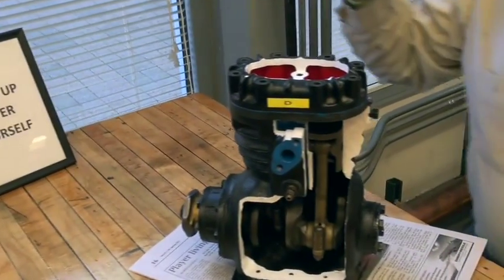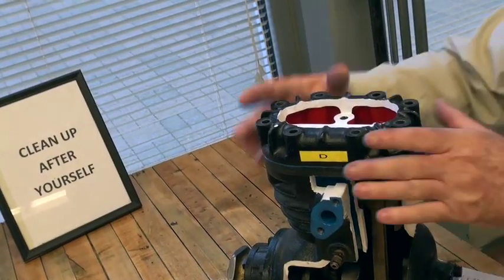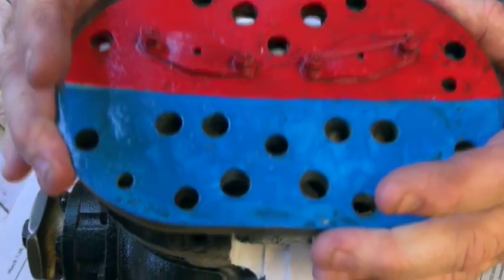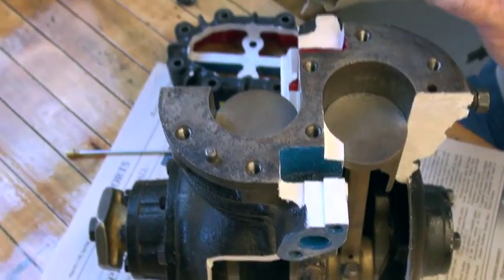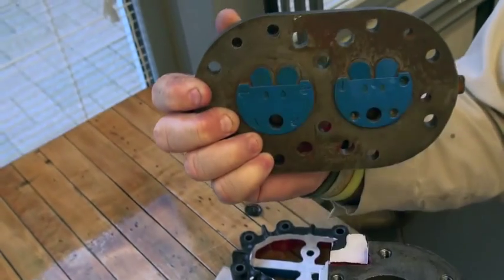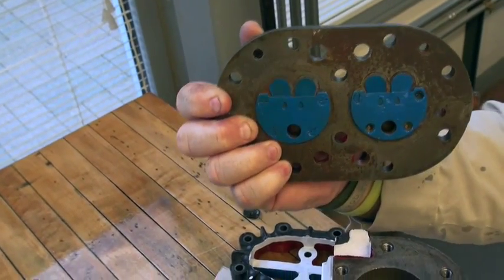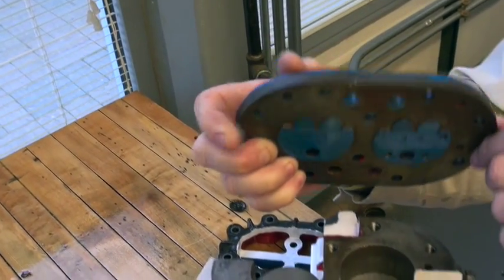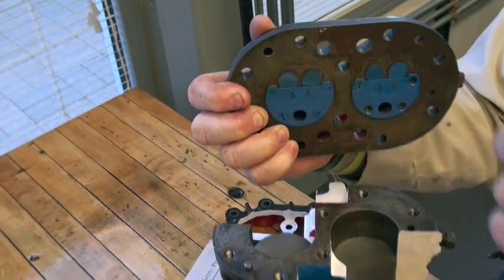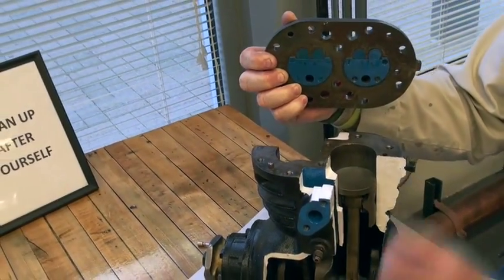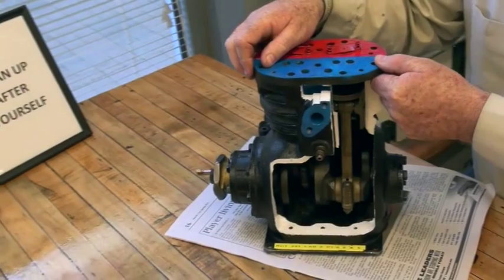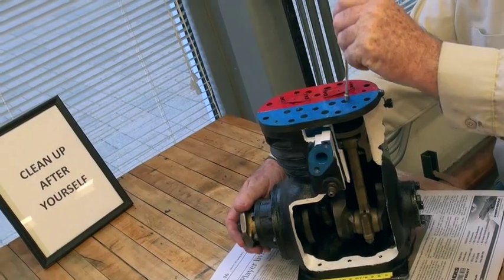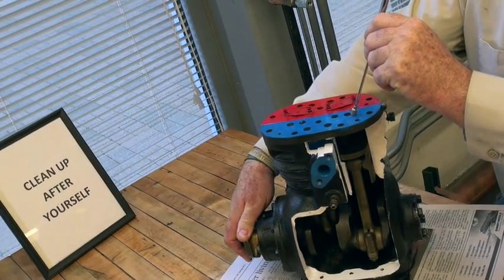When that drops, you can lift this off and you can see these little butterflies, all right? Those are valve seats. Those valve seats are designed to open only on one side as it draws down, right? So, in this case, the refrigerant would be sucked in on this piston as it draws down.